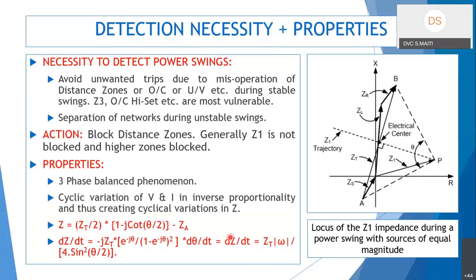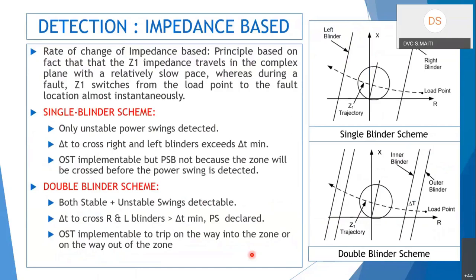The impedance seen from the relay to a load point is Z1, and its change is related to the change of the rotor angle. During a power swing, the load point impedance comes inside the distance zone. For an unstable swing it goes out the other side; for a stable swing it comes inside and returns back.